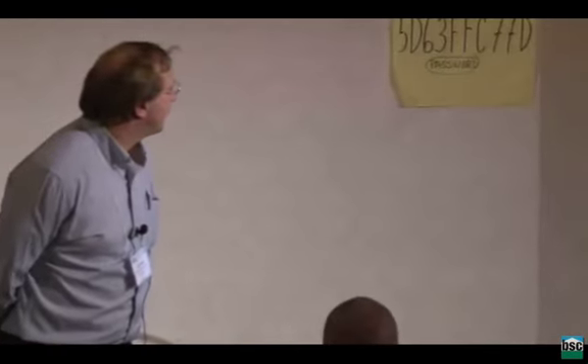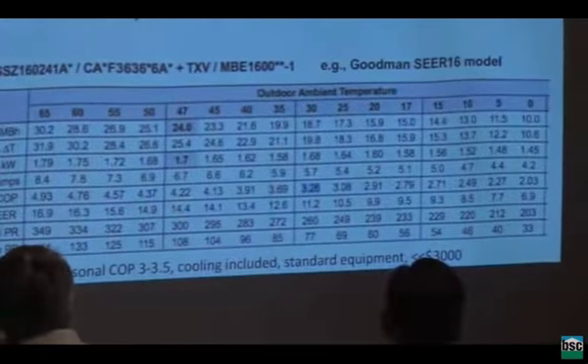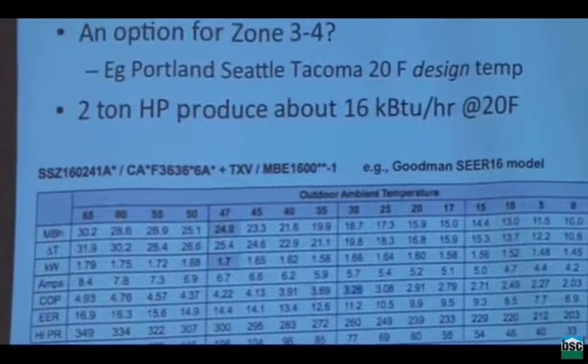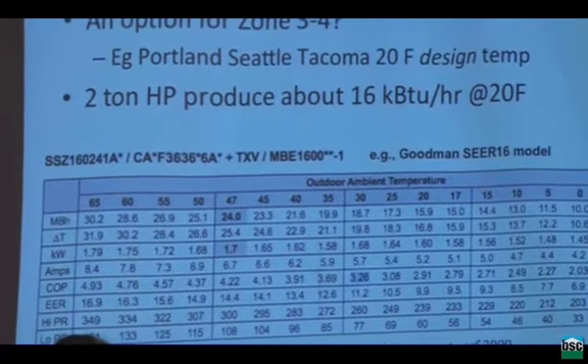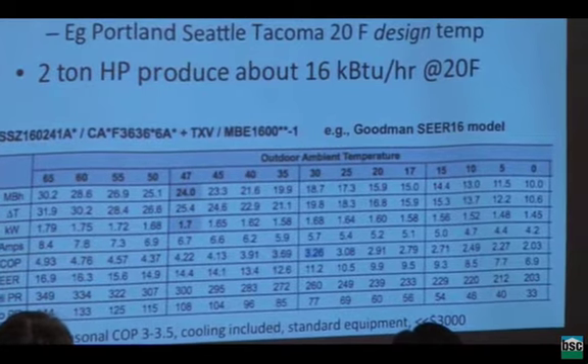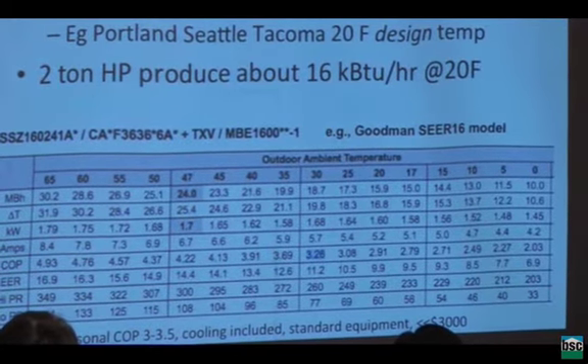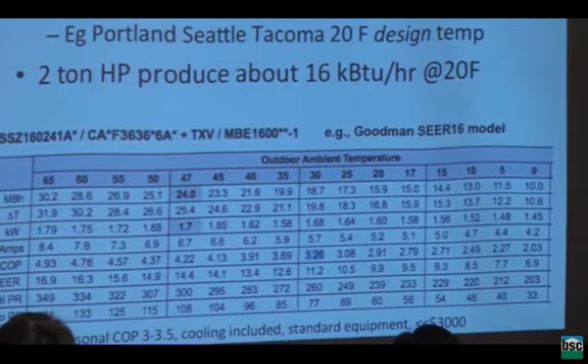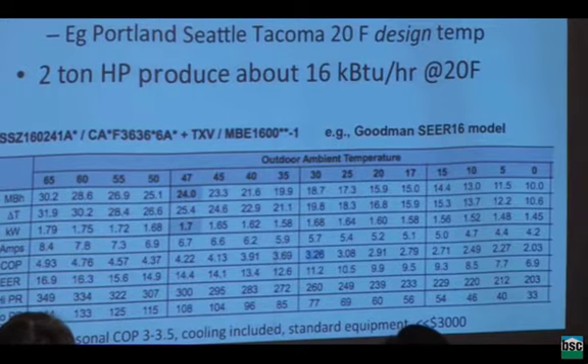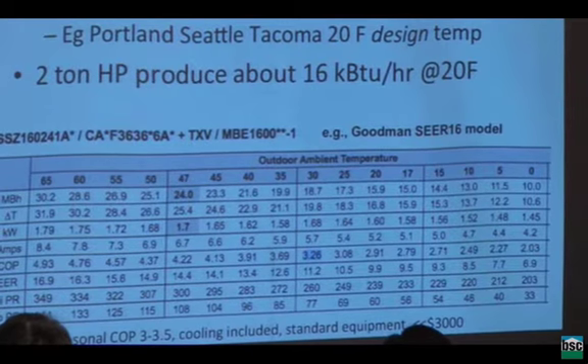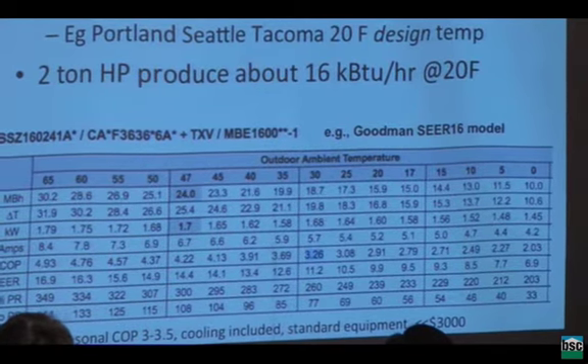You can see that at 20 degrees outdoor, we have a COP of 2.9. It's pretty good for Seattle. And if they're spending a lot of their time at 35 degrees outdoor temperatures, the COP is 3.7. That's actually really good. It means you're getting 3.7 units of heat for 1 unit of electricity. And that includes everything, right? It's a packaged unit, fan, compressor, everything. Not a bad solution. If I go to Boston and use this, it's a 5-degree design temperature. I only get 11,500 BTUs an hour, which might be fine for a really small or really efficient house, but not for your house. And now the COP is down to 2.27. So you see the efficiency is dropping as well as the capacity. So it doesn't work that well at these really cold temperatures.